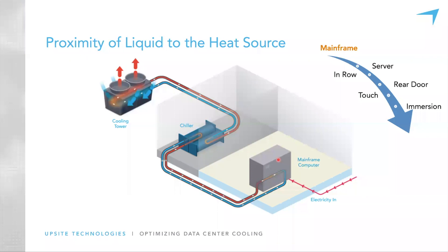Starting in the mainframe days, we've got a big box sitting in the computer room on the slab or the raised floor, and we've got chilled water flowing through the chassis picking up that heat and taking it out with liquid. It likely goes to a chiller where the heat is transferred to condenser water, which carries the heat out to a cooling tower where it is ultimately rejected to the atmosphere.